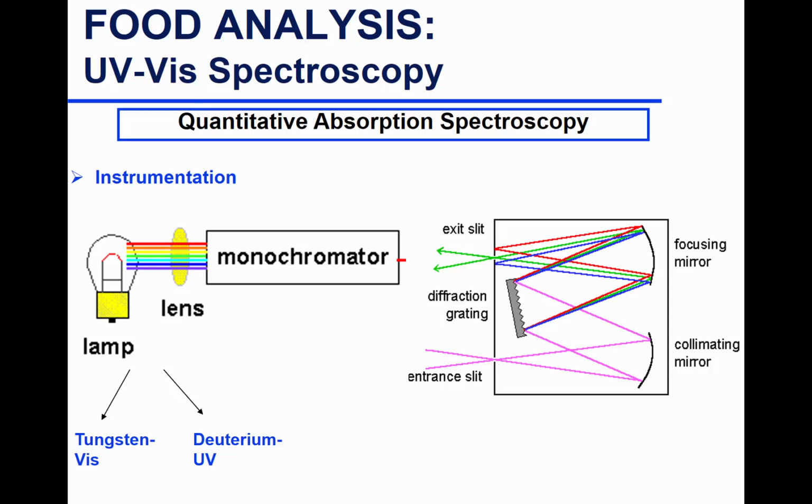Okay, and this slit you can select oftentimes, many times, unless it's a fixed UV wavelength detector. You can select where that slit goes to allow different wavelengths to pass through. And remember last time we said that we have mirrors. You want to make sure everything fits in a small box and the light goes in and goes out in a different direction. So mirrors usually are used to reflect the light.